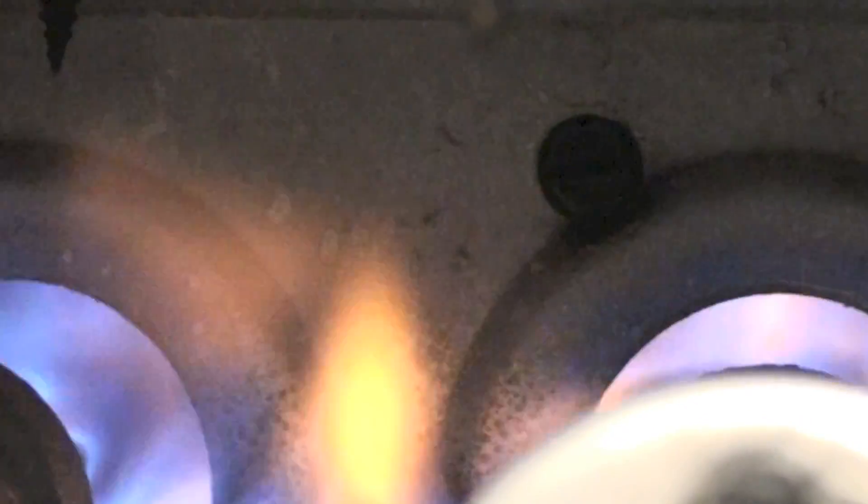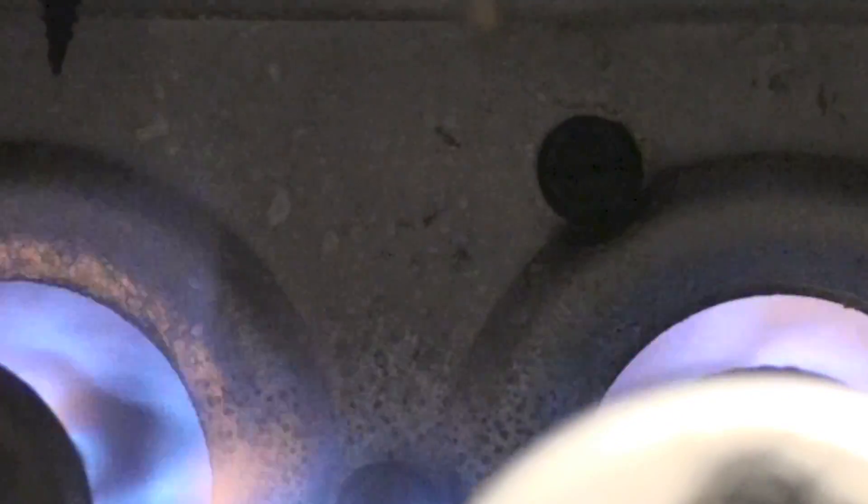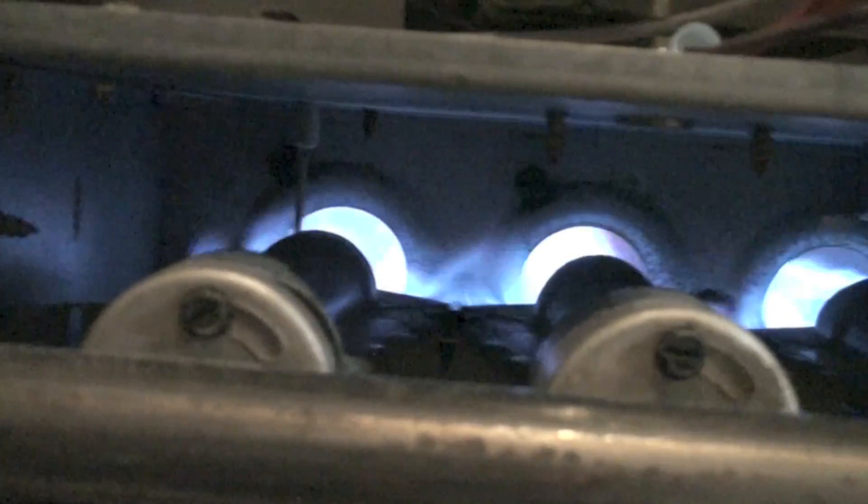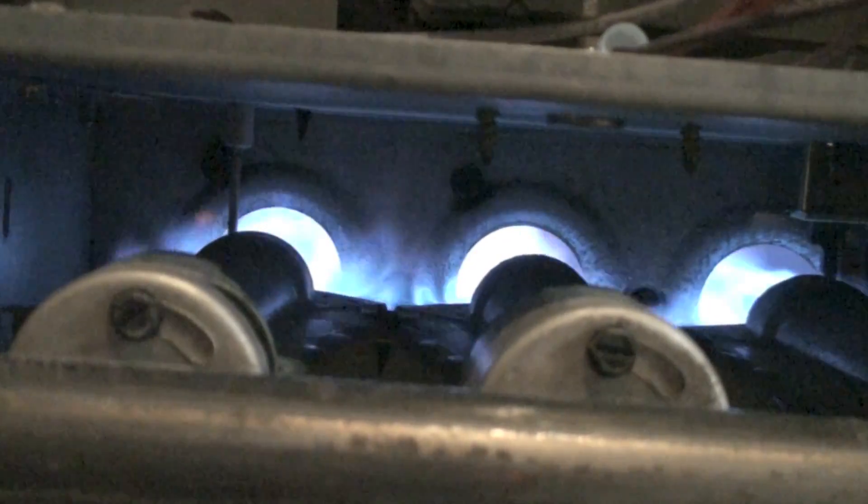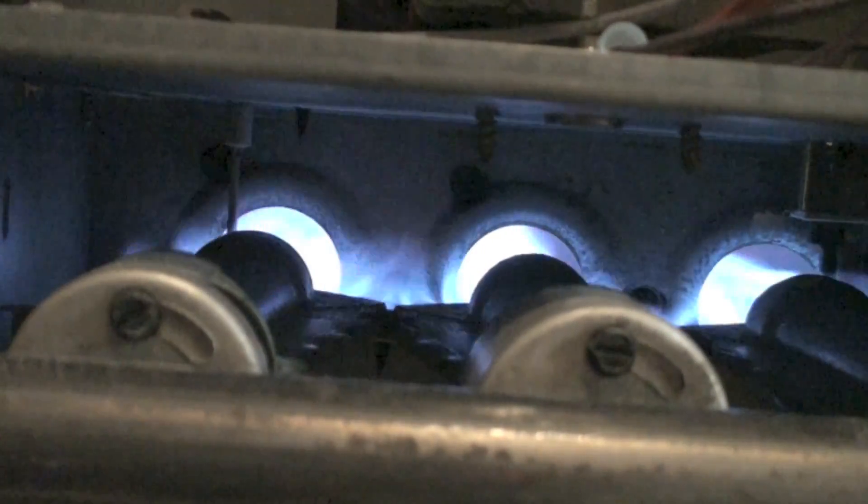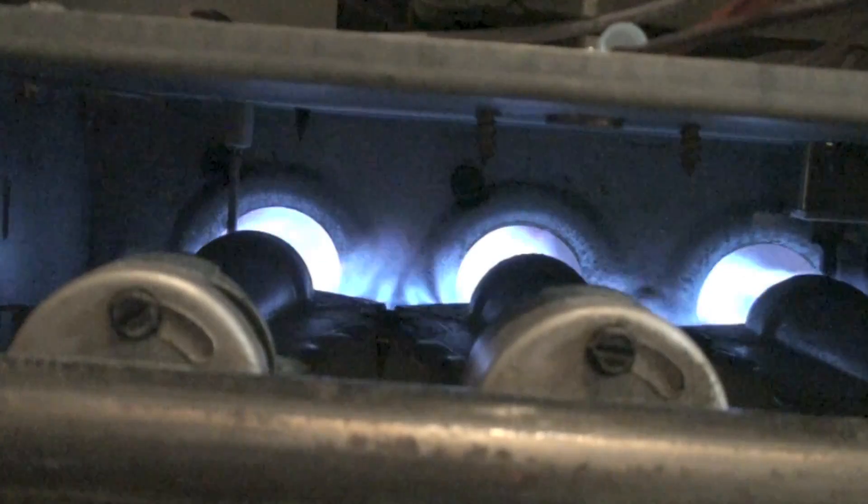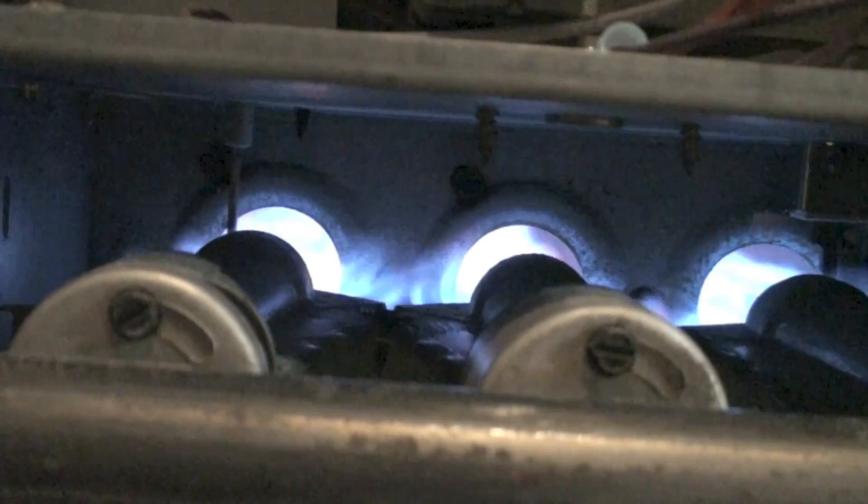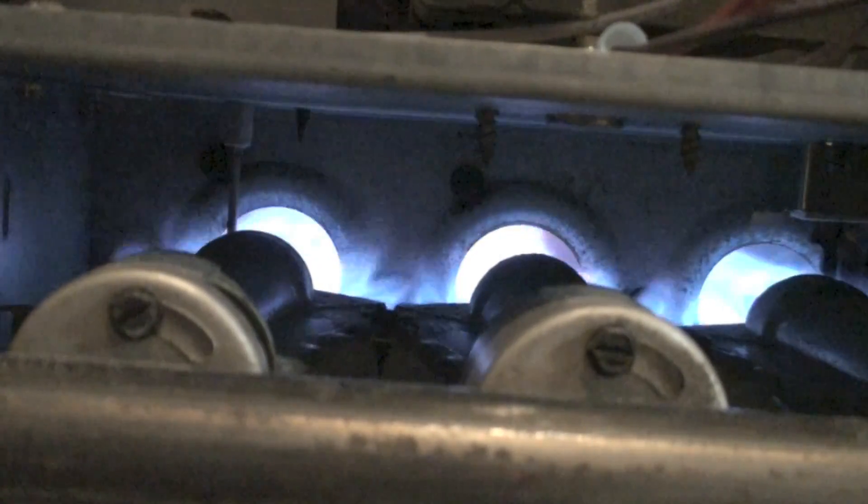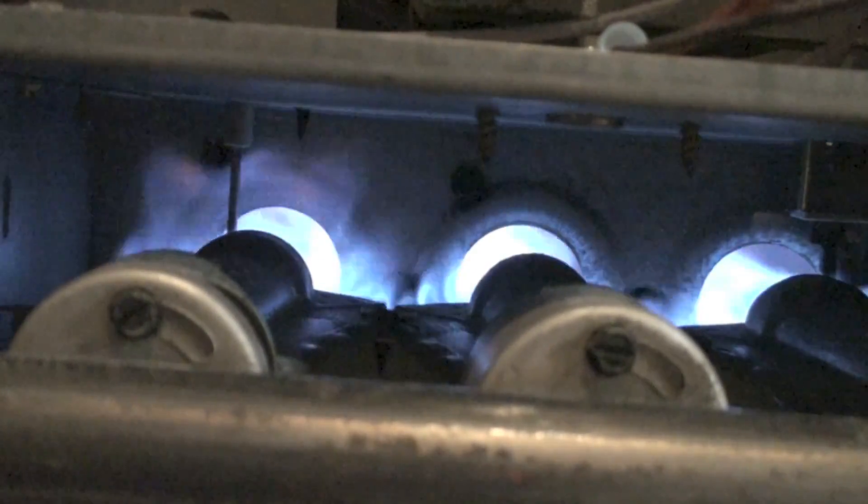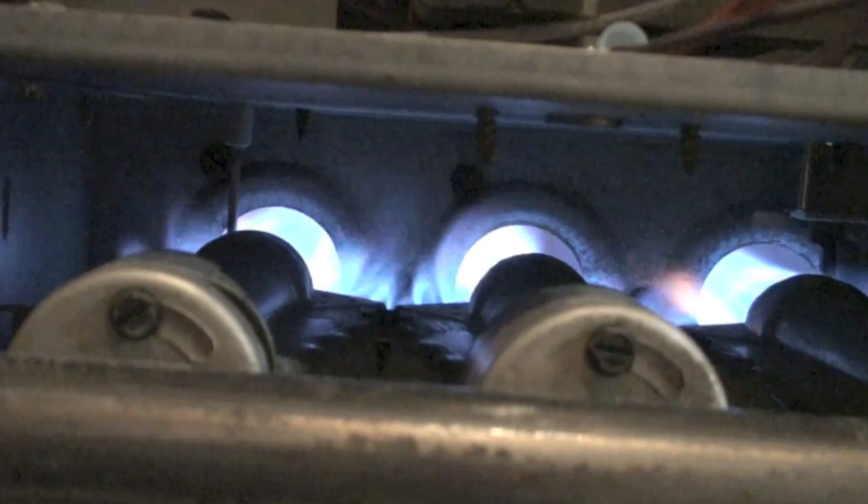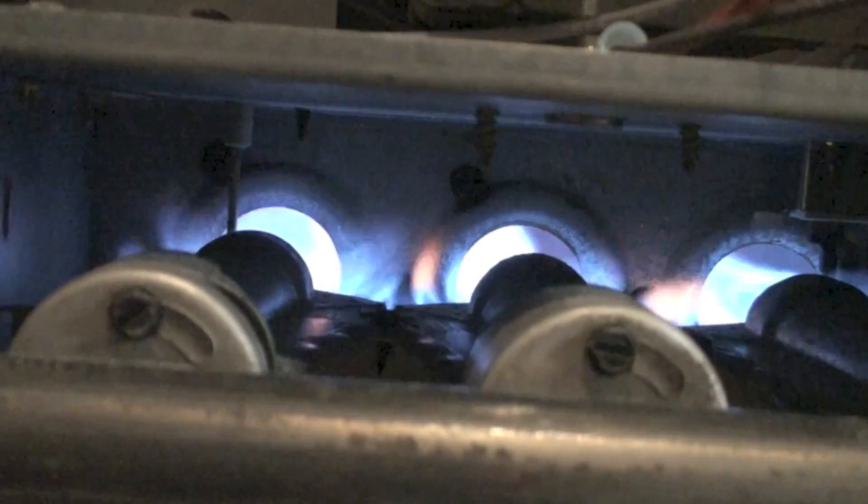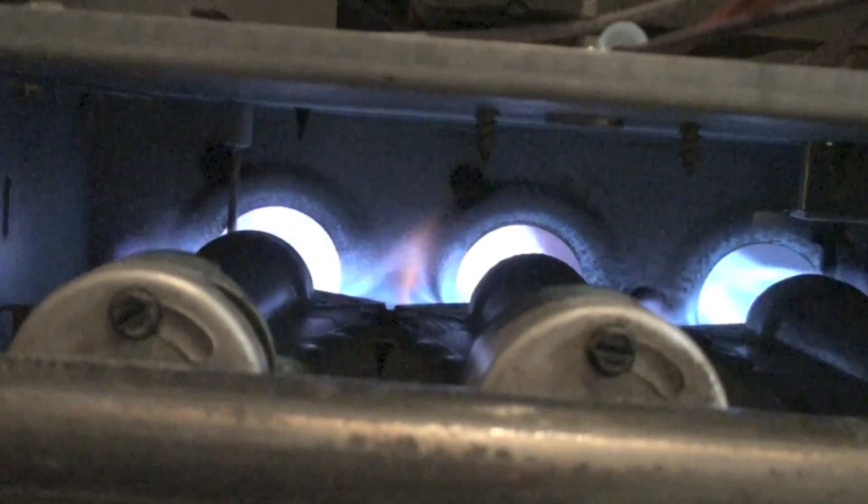Now this one here has problems because it has cracked heat exchangers, so the flames are coming out the front. You want to make sure nothing like that's happening. If something like that's happening, stop the service right then and start inspecting that heat exchanger. There's no sense going any farther if you've got problems like that.